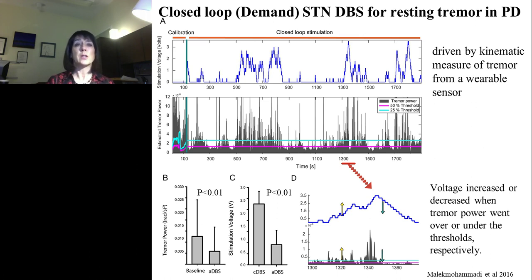Using this kinematic closed-loop system, we showed that it was efficacious, meaning it had a statistically significant improvement in tremor, using less than 50% of the voltage that the stimulator would have used in the open-loop mode. And the stimulator was actually on roughly 51% of the time it would have been on in the open-loop mode. So this was quite a dramatic savings of energy.